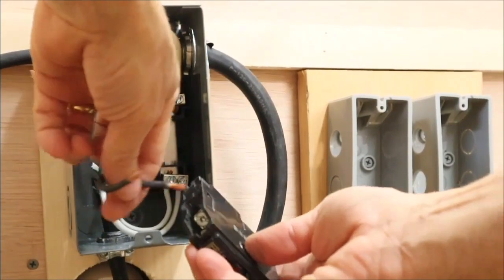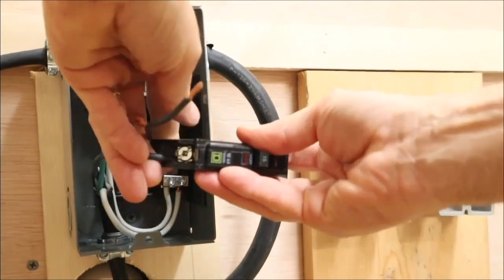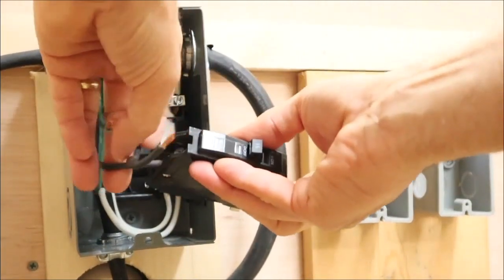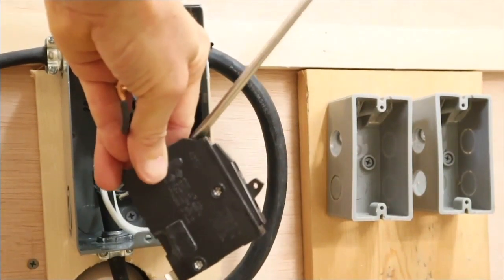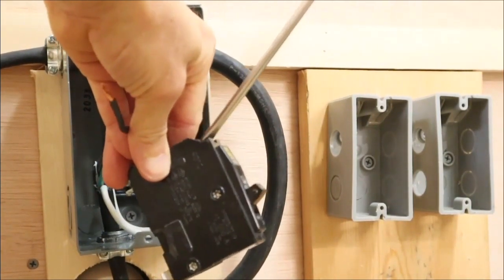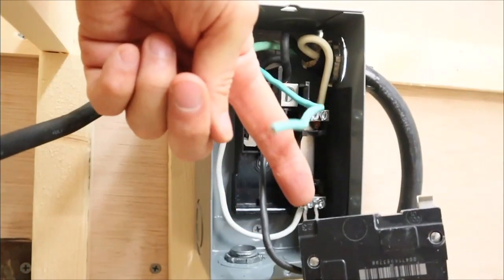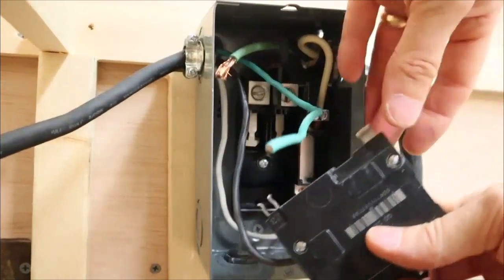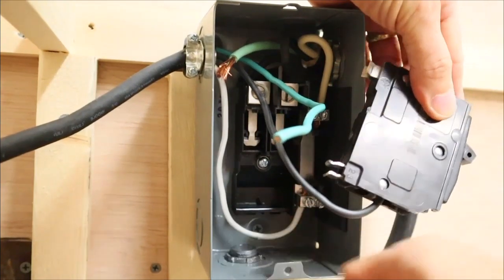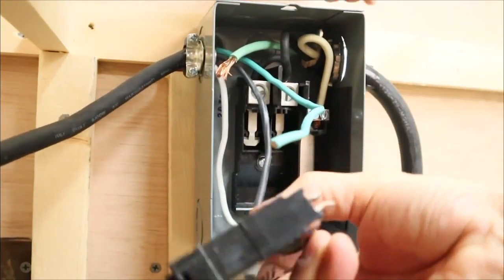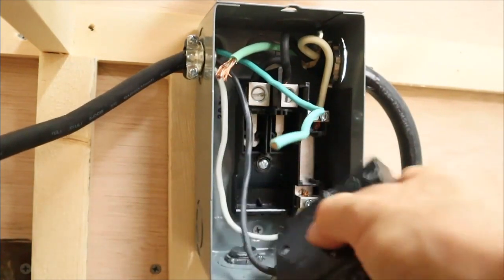The black 12-gauge wire from each electrical box hooks up to a breaker for that electrical circuit. So I'm going to have a left circuit and a right circuit, and I'm going to have a left breaker and a right breaker. The left breaker will attach to the black wire from the left circuit. The way this breaker installs is the horizontal clamps clamp on the bar at the bottom. You have to push in with a little bit of force. Then the vertical clamps will clamp at the bar at the top.